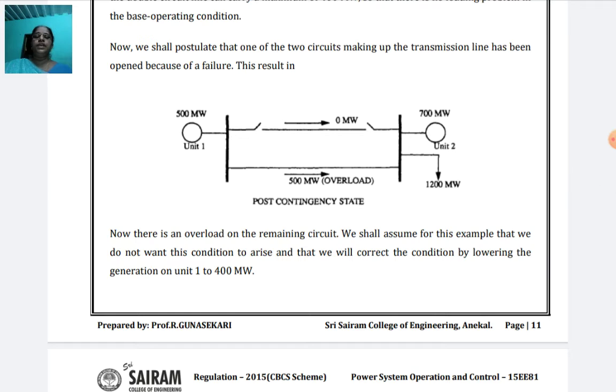Second one is the post contingency state. In the post contingency state, you see line 1 is opened. So 0 megawatts, that means open only; line 1 is not able to carry the load. So now what happened? Line 2 has to carry the 500 megawatts from unit 1 alone. So line 2 becomes overloaded. If overloaded, there is a chance of a line outage in transmission line 2. This is the post contingency state, that means after the contingency occurs. What is the contingency? Line outage only.